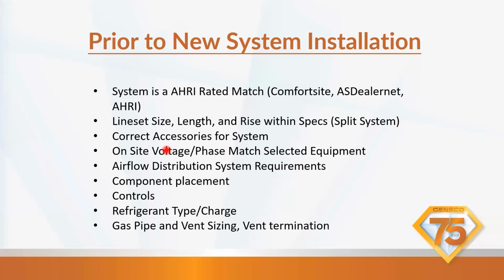Line set size. Make sure we got correct accessories for the system. Thanks everybody for your patience. On-site voltage phase match. That comes into play when we're having the three-phase on rooftop units. So we always want to confirm that we have correct voltage. Also, we have been seeing a spike in residential incoming line voltage. So everybody just be aware, we have had reports of 256 line voltage. So that is something to always double check. If we have high voltage, that could be affecting our circuit boards and everything in the house also.